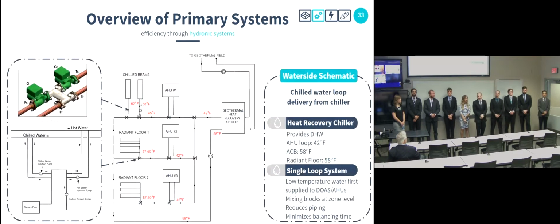The geothermal well field supplies heat rejection and heat regeneration to our bank of Multistack heat recovery chillers. This modular chiller system can be quickly installed, and it also can be used as staged compressors to allow for high efficiency at part load conditions. The hot and chilled water loops utilize modified single loop systems. The chilled water loop shown here shows that chilled water is first delivered to the AHU units and then to the chilled beam and radiant floor zones. This allows us to use a lower head loss on the secondary circulation pumps, and also reduces installation time since the single loop pipe sizing is the same size throughout the building.